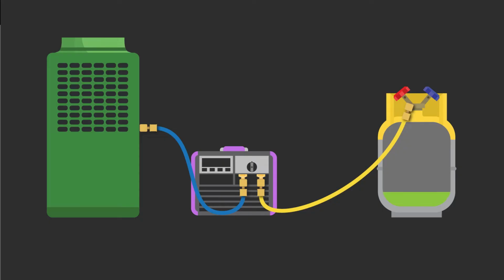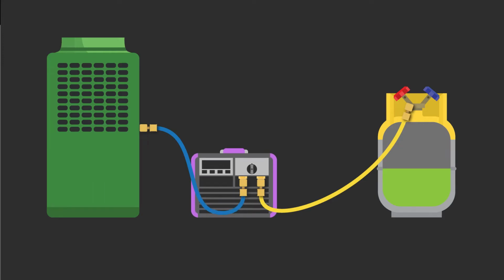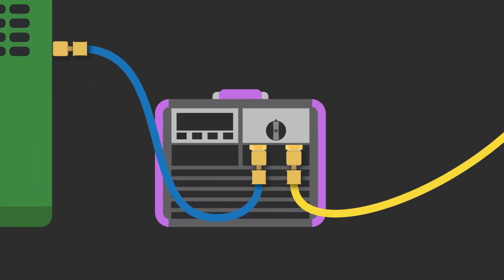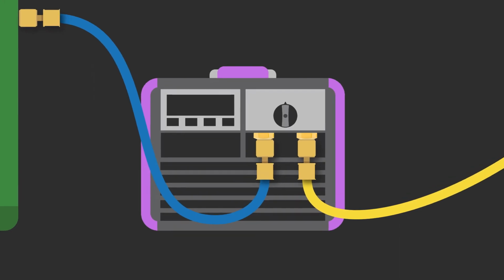However, moving liquid refrigerants can present challenges for some recovery machines. Most recovery machines are unable to recover liquid refrigerant due to the risk of internal component damage. A common workaround that some recovery machine manufacturers incorporate is a throttling knob to control the amount of liquid that is entering the compressor. While throttling refrigerant does help avoid liquid hammering and potential damage, it comes at the cost of restricting the refrigerant flow, ultimately slowing the recovery process.